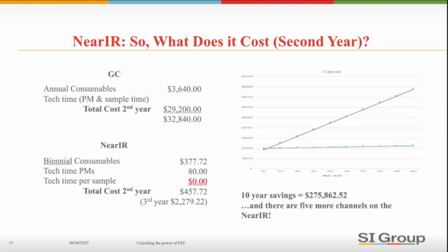The second year, GC consumables and technician time stay the same, as they do for every consecutive year. The NIR, on the other hand, needs only a halogen lamp replaced. They usually last about 1.5 to 2 years. No technician time is needed because the instrument runs all by itself. The third year, GC costs remain the same. A laser may be necessary for the NIR, though newer technology is extending laser replacement times.